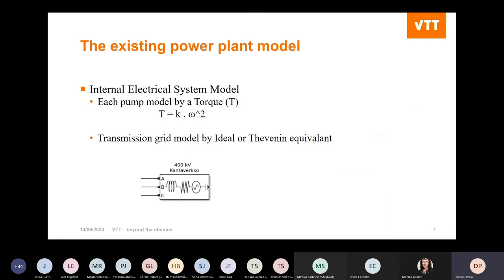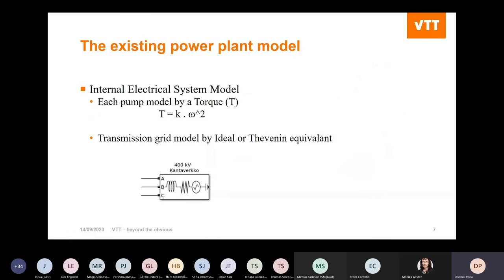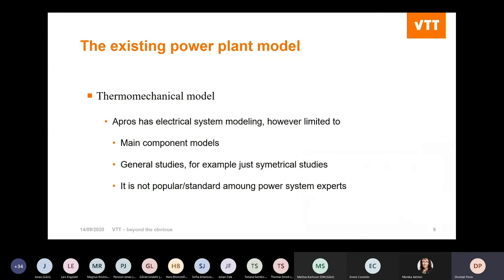Similarly, to represent the high-voltage system, a kind of ideal or Thevenin equivalent — a fixed equivalent — is used, holding the transmission system at one fixed value. On the other hand, when thermomechanical software like APROS is used, the electrical system is modeled as a very simple symmetrical model. It cannot simulate many events like a single-phase fault or any asymmetrical condition.